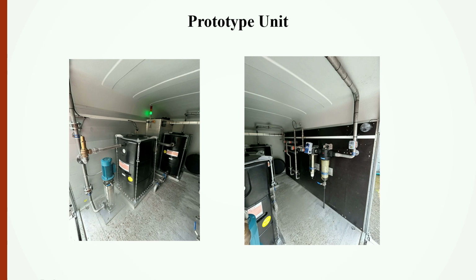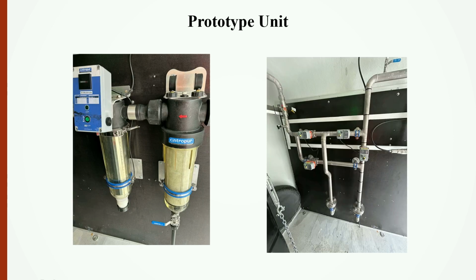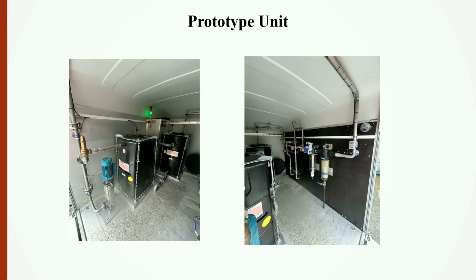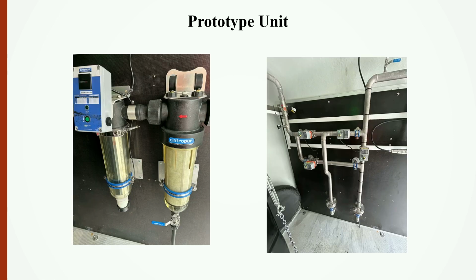If we go to the other side of the container, we have the treatment system there, and then an arrangement of valves which will divert the flow through the first sequence and then the second sequence. In close-up, there's a filtration system there which will take it down to about 5 microns, and then we have a UV sterilizer which will zap the bacteria so no bacteria are introduced into the loop itself.